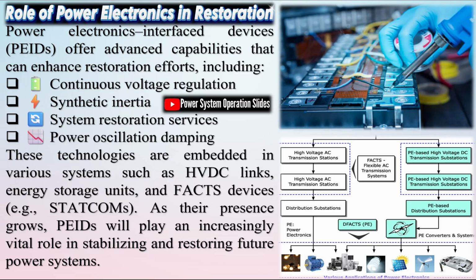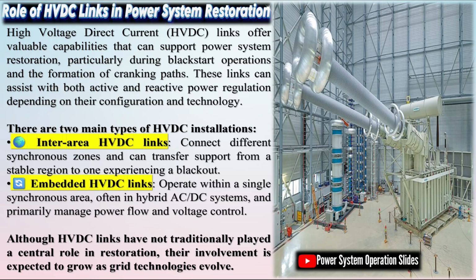Inter-area HVDC links connect different synchronous zones and can transfer support from a stable region to one experiencing a blackout. Embedded HVDC links operate within a single synchronous area, often in hybrid AC-DC systems, and primarily manage power flow and voltage control. Although HVDC links have not traditionally played a central role in restoration, their involvement is expected to grow as grid technologies evolve. Technology types and restoration applications.